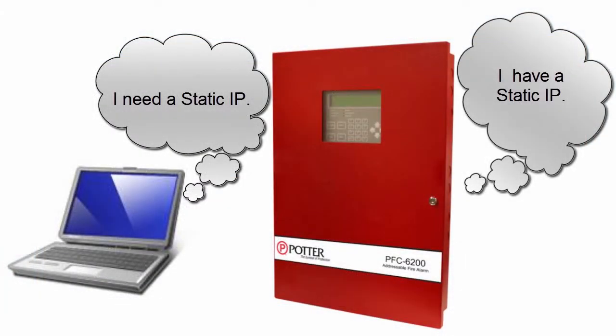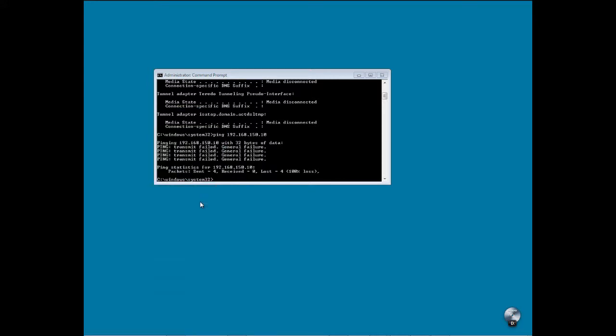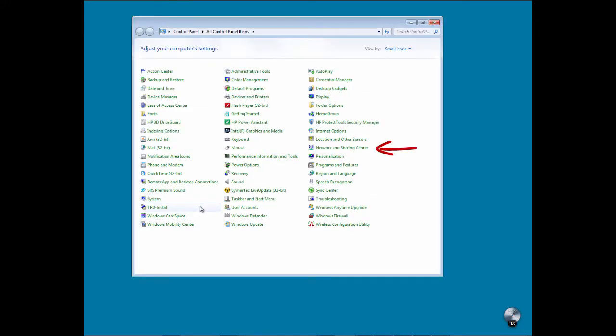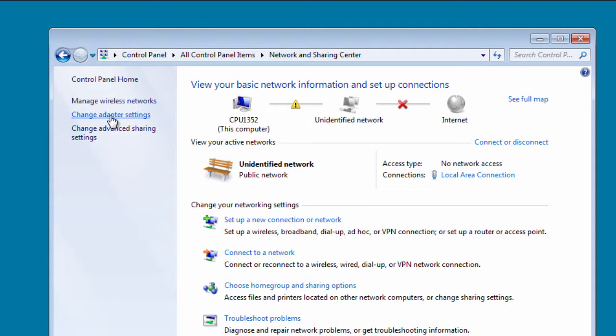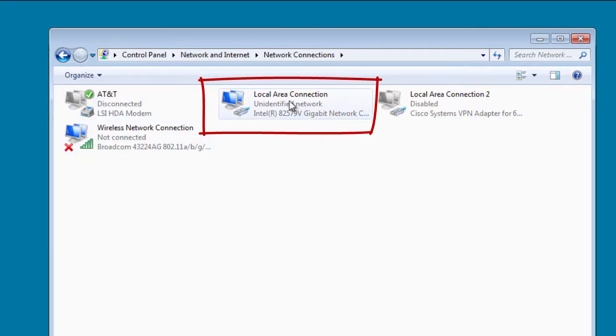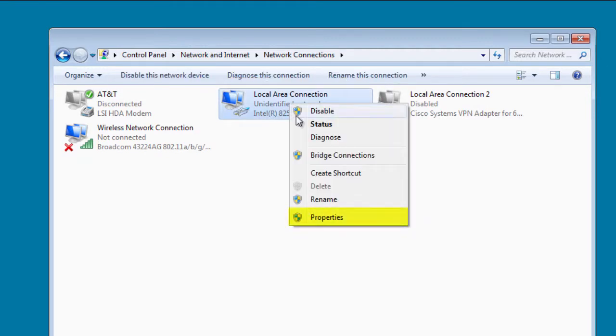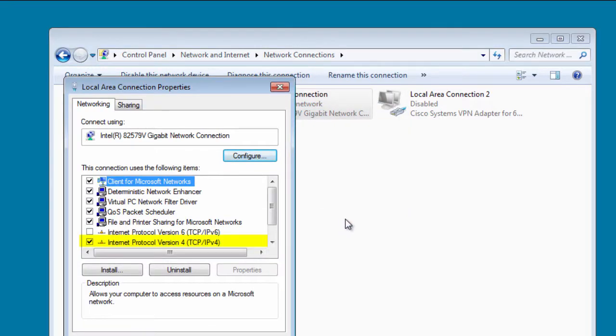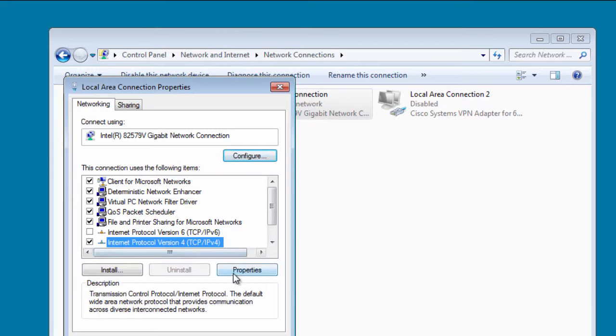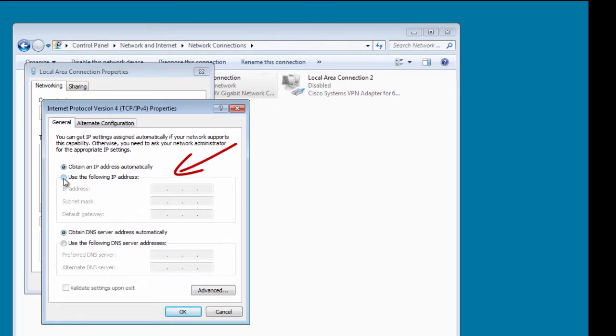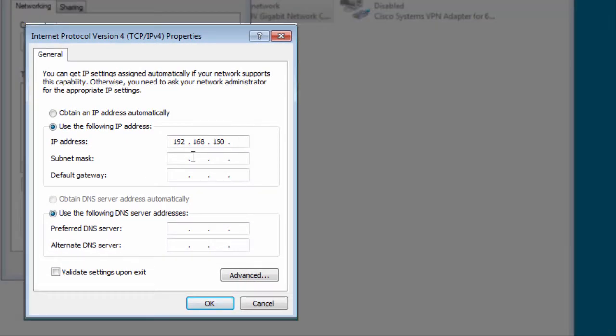If a static IP needs to be assigned to the laptop computer, go into your Control Panel — start menu, select Control Panel. From here, select Network and Sharing, then Change Adapter Settings. Go to your local area connection, right-click on it, and select Properties. We are working with Internet Protocol Version 4, so select Internet Protocol Version 4, get it highlighted, and then select Properties. From here, I can set a static IP by selecting the radio button "Use the following IP address," and type in 192.168.150. Since the fire alarm control panel is .10, I'm going to select .9.